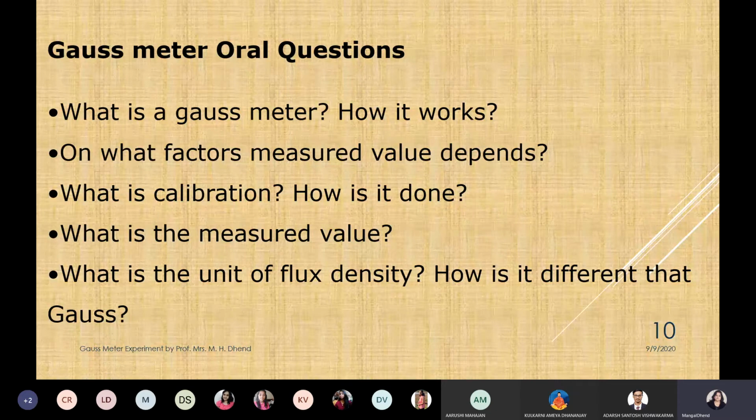I know, you also know. So you measure that 10 Gauss with the help of same device, Hall voltage Gauss meter. And you will not get flux density 10, but you will get 9. So you find that constant is changing. You just check whether ammeter reading is 0 when current is 0, or you just make that 0 adjustment of ammeter. You just see voltmeter, whether voltmeter is reading 0 when voltage is 0 or no. If it is not showing 0, you make that voltmeter to read 0. So that you take care of your ammeter, you take care of voltmeter, then again check your flux density.